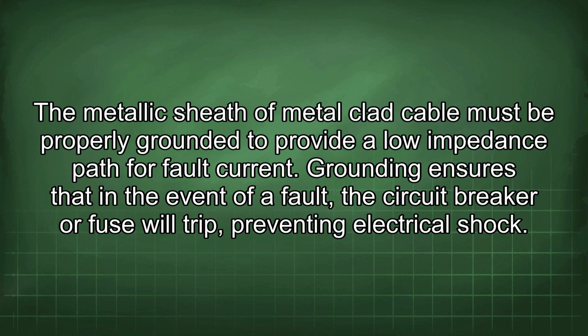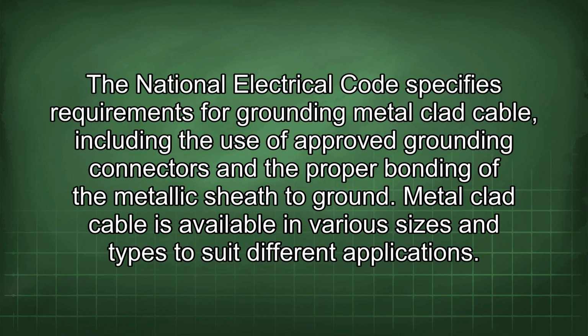The metallic sheath of metal-clad cable must be properly grounded to provide a low-impedance path for fault current. Grounding ensures that in the event of a fault, the circuit breaker or fuse will trip, preventing electrical shock. The National Electrical Code specifies requirements for grounding metal-clad cable, including the use of approved grounding connectors and the proper bonding of the metallic sheath to ground.